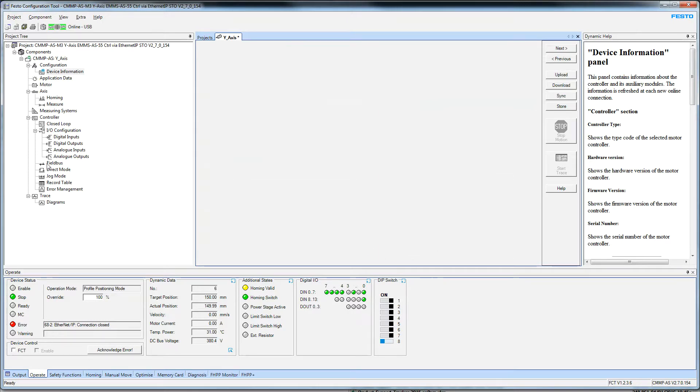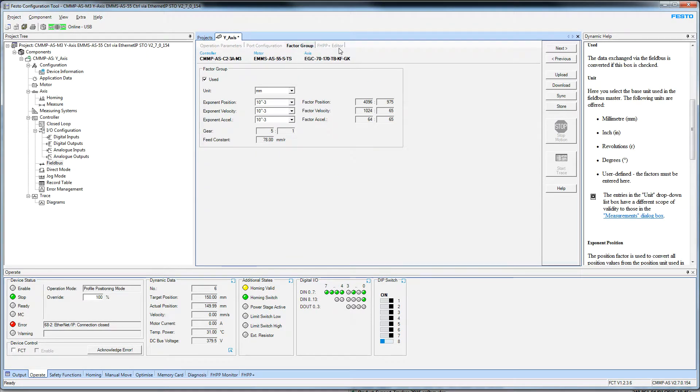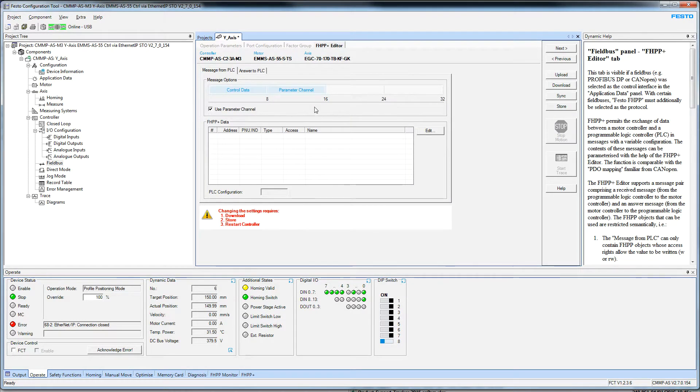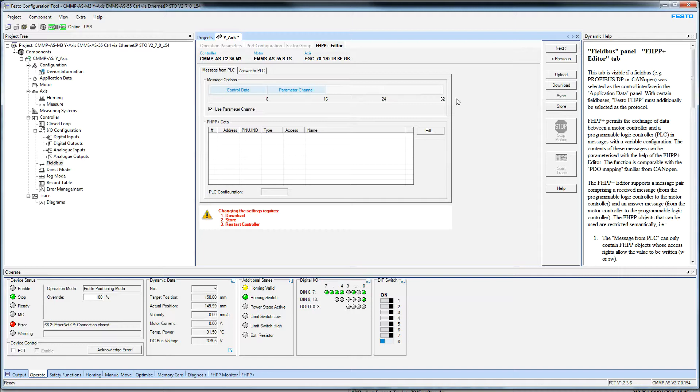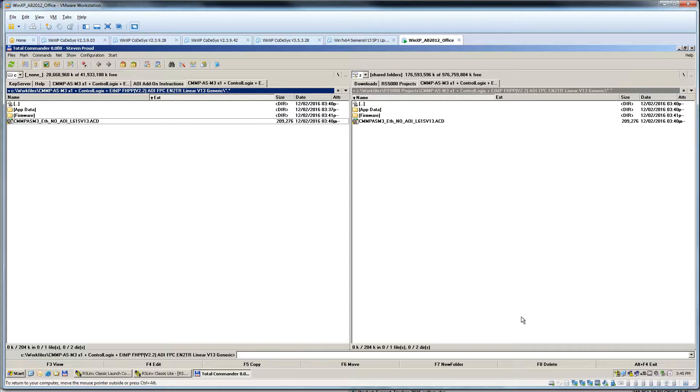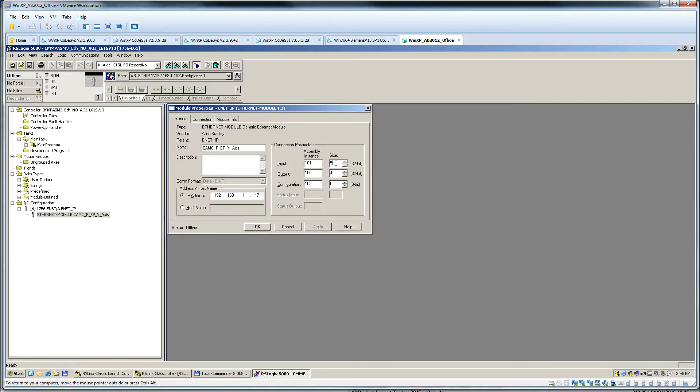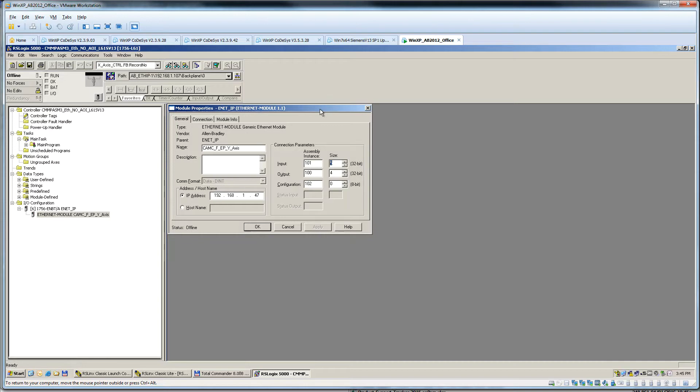Version 2.3 is what this is covering here. When you have this factor group configured with FHPP, you've got 16 bytes in and out. When you're on version 2.3 using a generic module in the Rockwell environment, your IO size is going to be an extra four bytes or an extra double integer for inputs and then the data because there's header information built in. I have not tested the EDS file. I'm just doing the generic module. Set up the IO size and away you go.